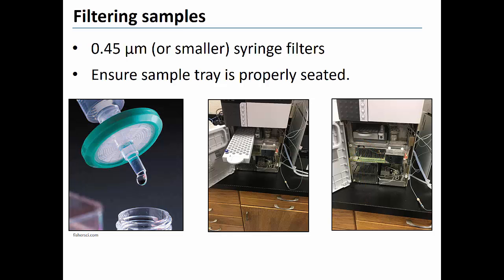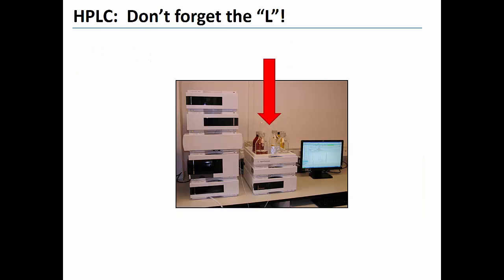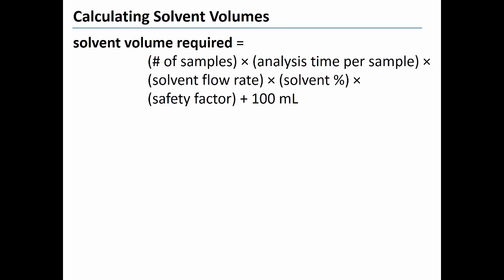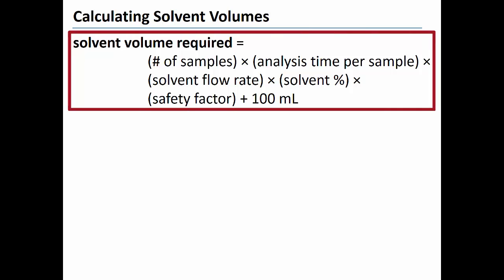An all too common mistake for HPLC users is running out of solvent. This is problematic because if a solvent level gets too low, the instrument will begin to pump air instead of solvent. Pumping air can damage columns and create flow obstructions in other parts of the instrument. Before beginning a batch of samples on an HPLC, it's important to estimate the total amount of solvent that you will need to complete that batch.